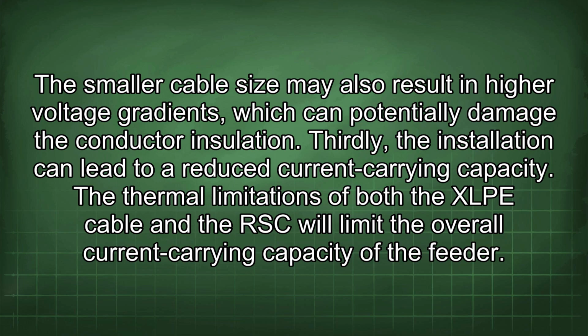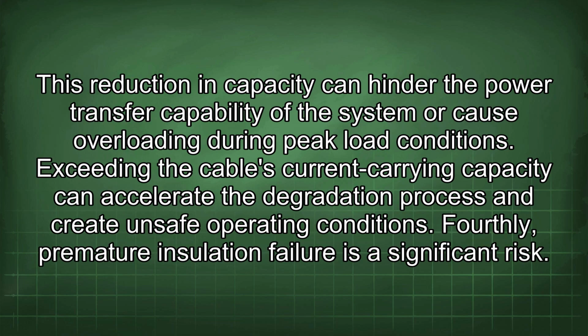Thirdly, the installation can lead to a reduced current carrying capacity. The thermal limitations of both the XLPE cable and the RSC will limit the overall current carrying capacity of the feeder. This reduction in capacity can hinder the power transfer capability of the system or cause overloading during peak load conditions. Exceeding the cable's current carrying capacity can accelerate the degradation process and create unsafe operating conditions.